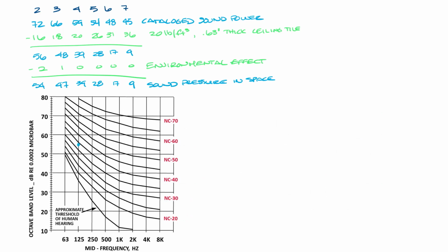And when we plot this in here, you'll see we get approximately NC37. So this product would sound like an NC37 in this space. Now let's scoot this over and let's look at the discharge sound.